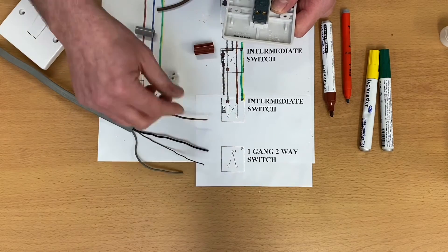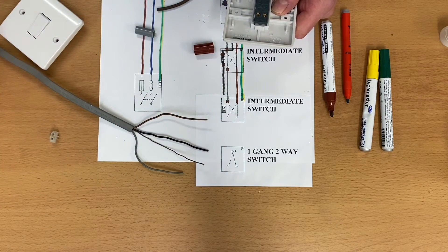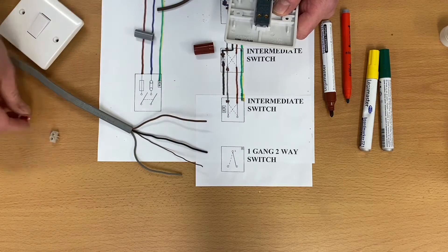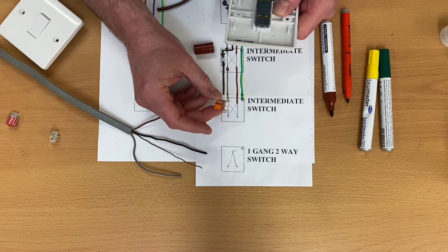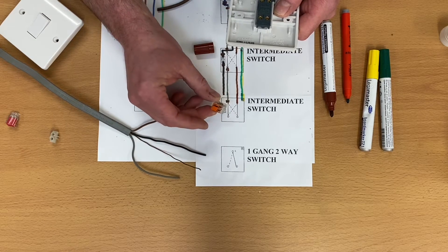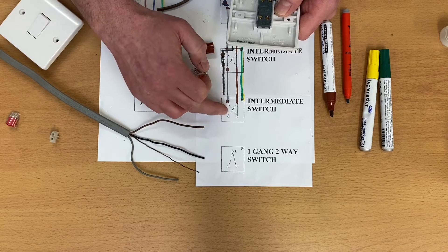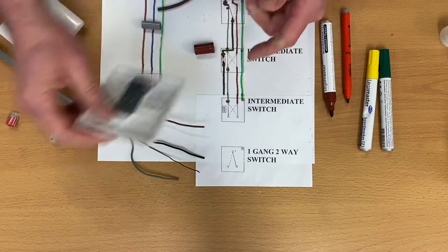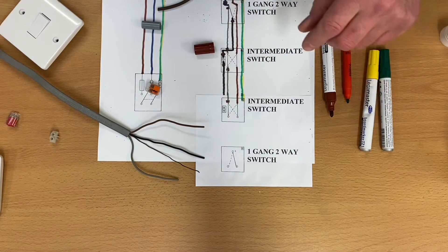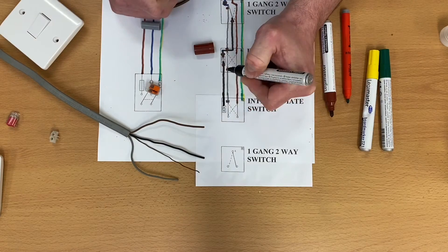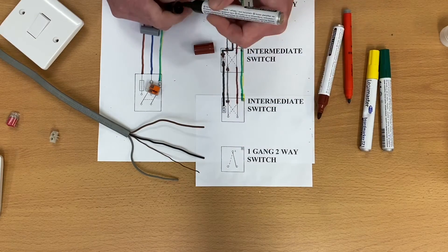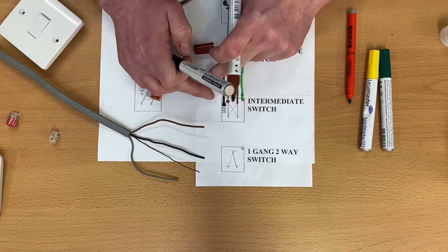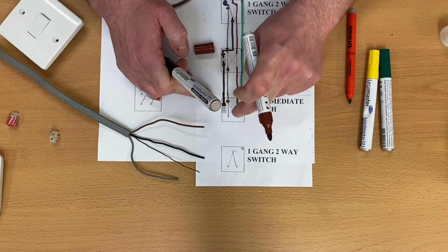And I've drawn a picture there of an old-fashioned five-amp connector block. Here, it could be a red through crimp, which I've shown in a previous presentation. It could be one of these style ones from Ideal Industries as a connector, or one of these WAGO connectors sometimes. If you're saying it correctly, it's actually VAGO, but we call them WAGOs, don't we? So that there is a connecting point, not within the switch itself. We make that connection as we did in our previous intermediate switch. So our black comes in and passes obviously out in a moment. Remember, we must put brown sleeving on that.